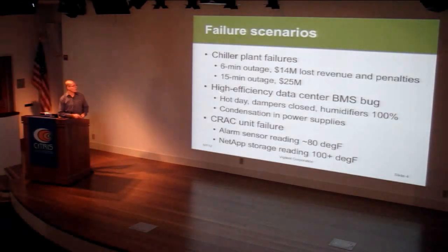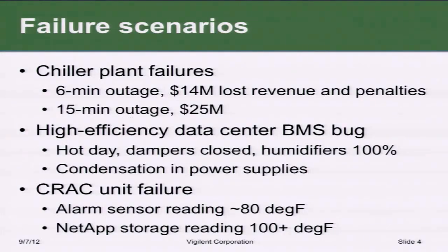Here's an example of one of these where on a hot day, where it was supposed to be bringing in hot but dry air, the outdoor air dampers closed and the humidifiers went to 100% because they had a bug in their BMS programming. This resulted in condensation forming in the power supplies and servers shutting down spontaneously. Obviously a catastrophic outage for that facility.